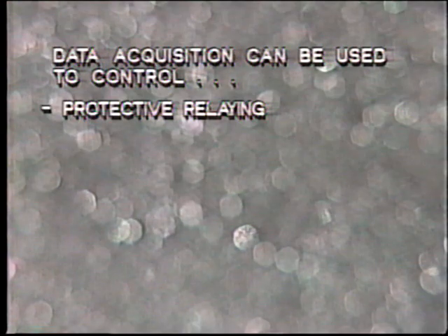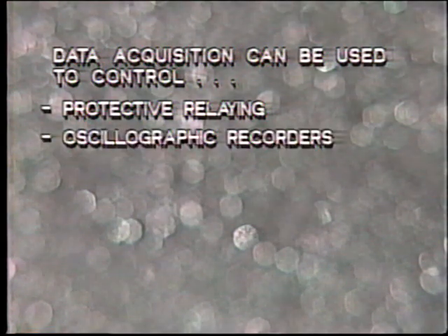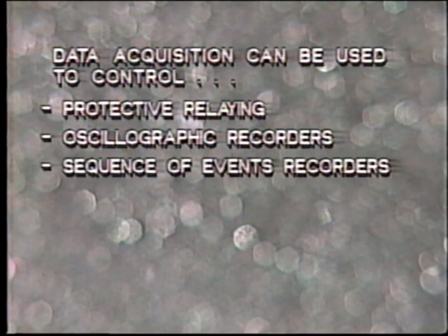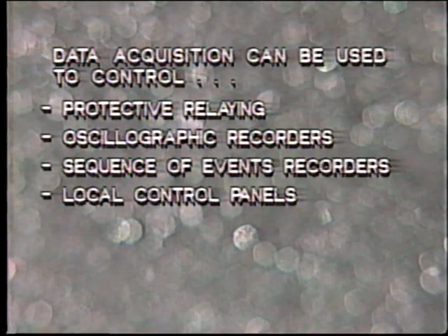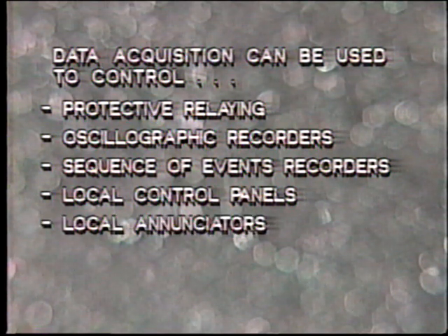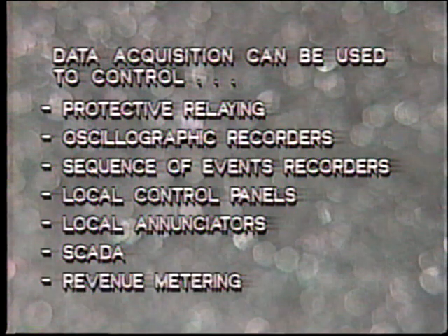We have mentioned several times the substation control system. This is a fairly new concept where the digital signals from data acquisition can be used to automatically control all of the substation activities, including protective relaying, oscillographic recorders, sequence of events recorders, local control panels, local annunciators, SCADA, revenue metering.